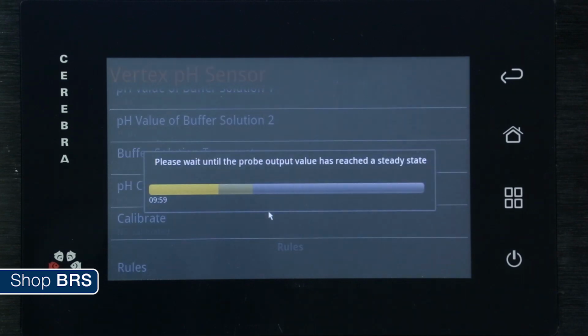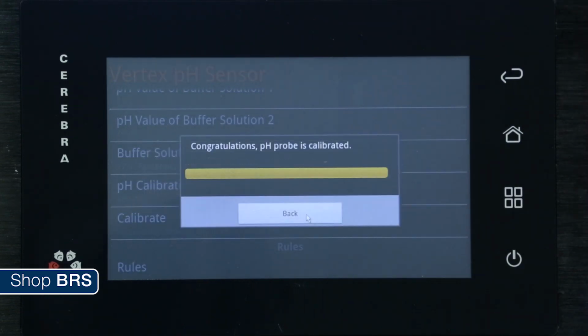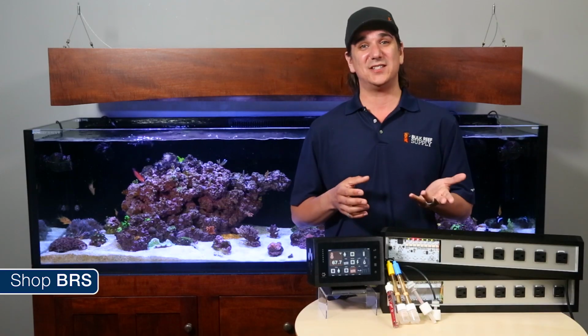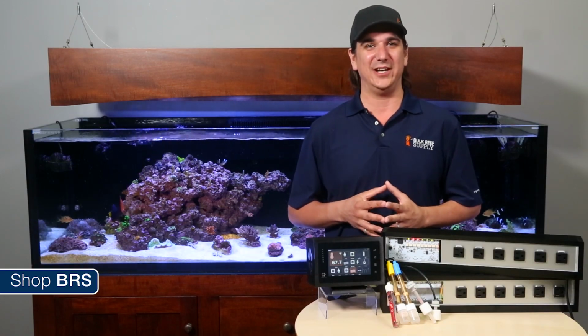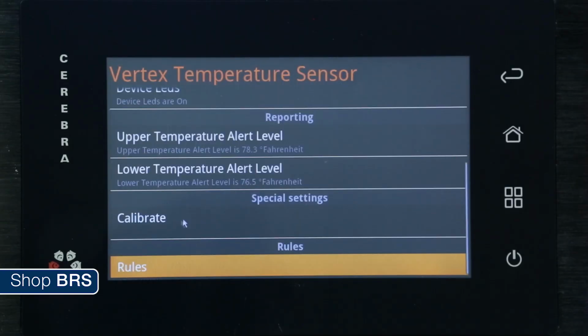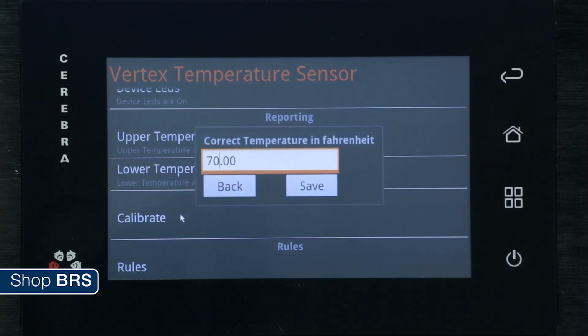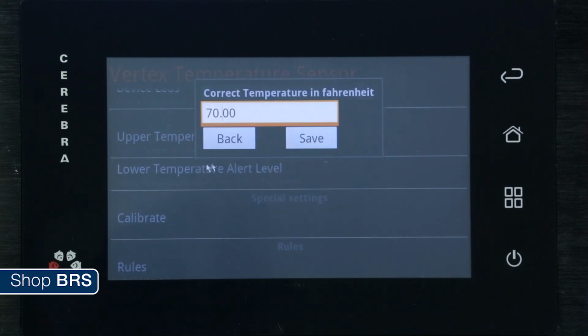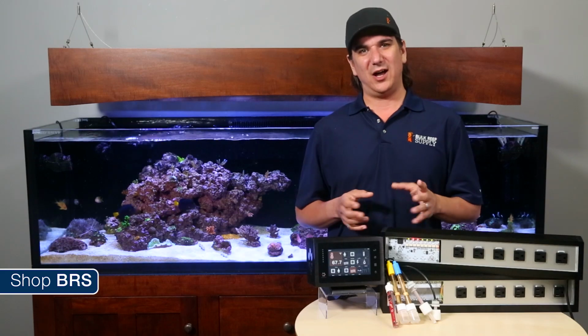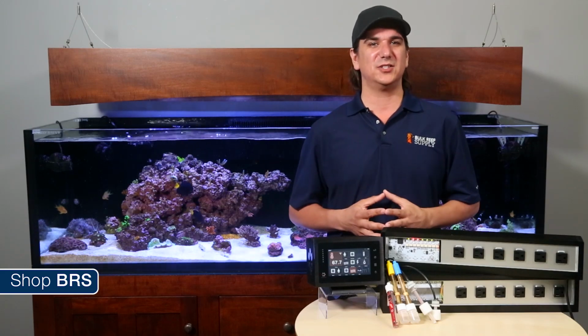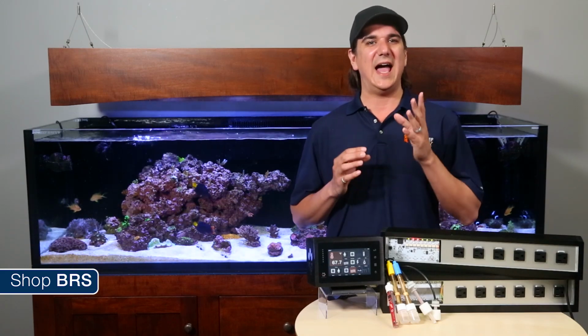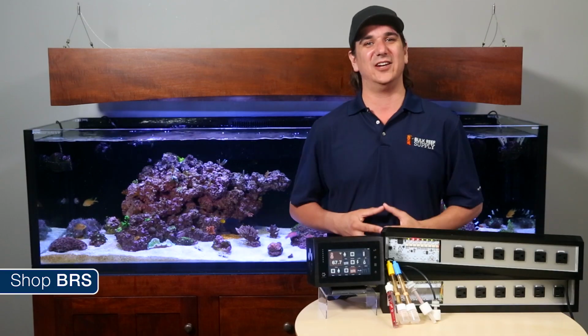It intelligently knows when to change the solutions and will even tell you the quality or condition of the probe that you're using at the end, I presume based on how quickly it was able to find the stable reading. Same thing for your temp probe. Click on the temp probe icon, calibrate, and enter your calibration temp based off your thermometers, and you're done. No mucking about in other interfaces or complex systems, just super simple, and again, anyone could figure this out without a single set of instructions.